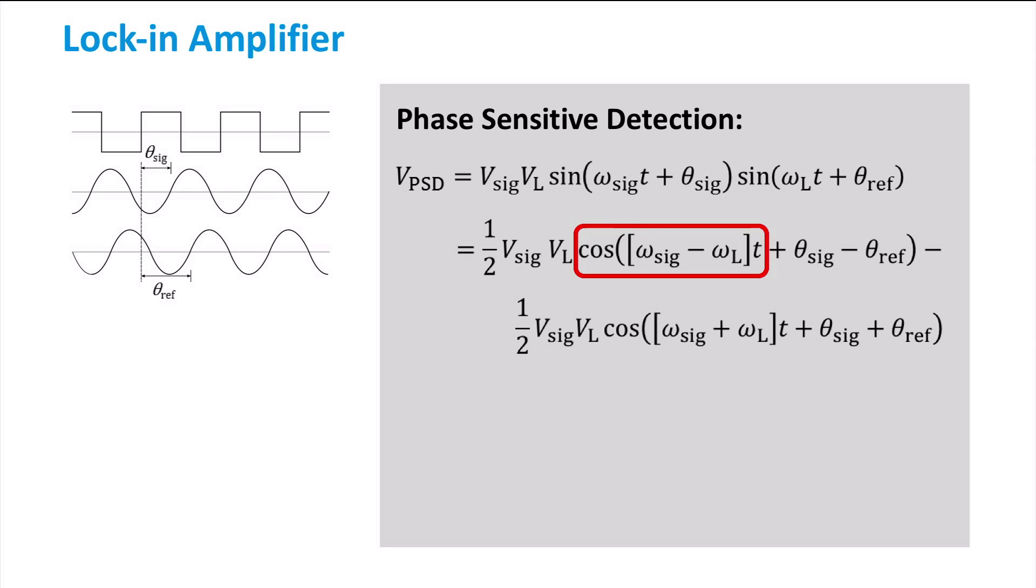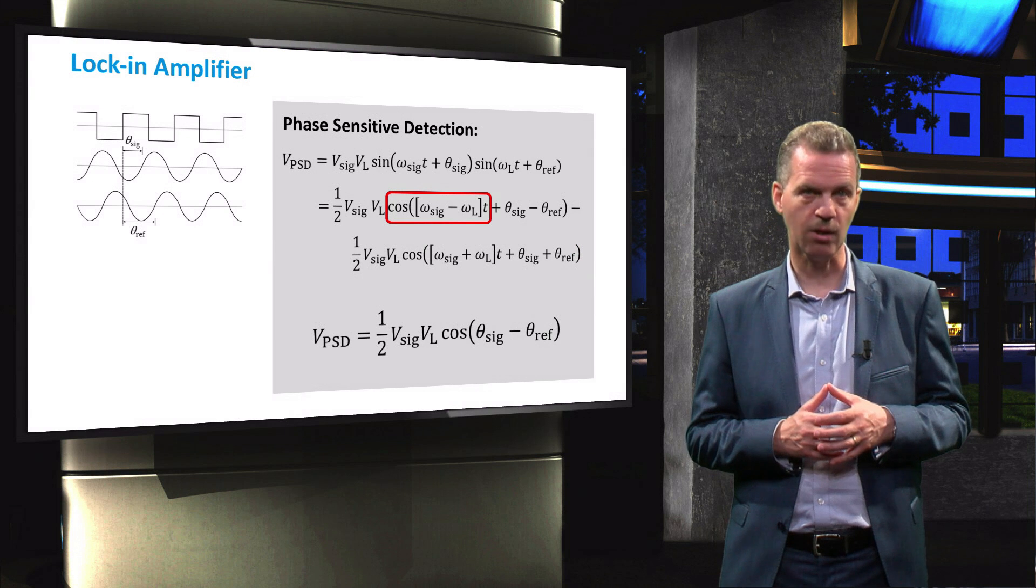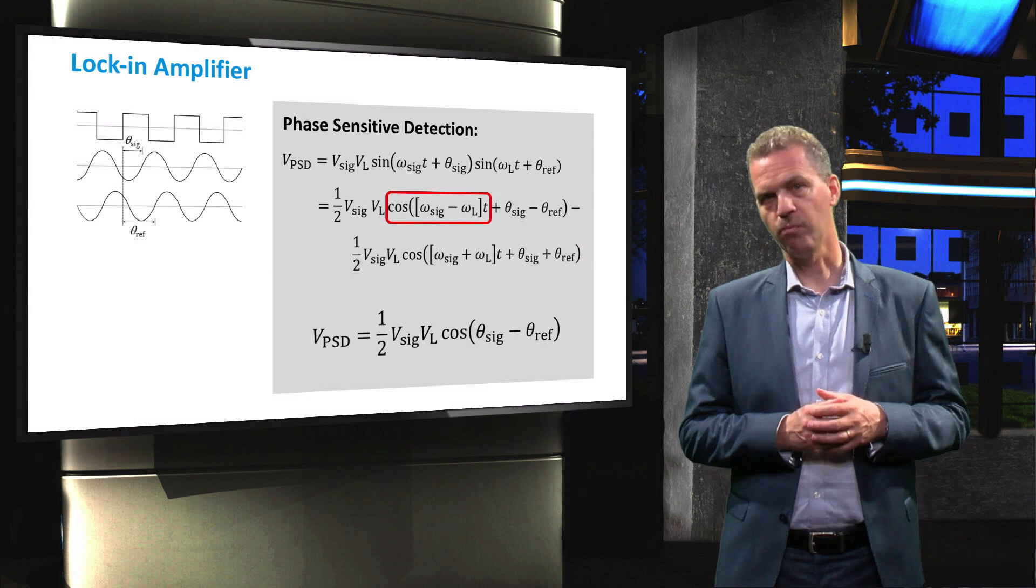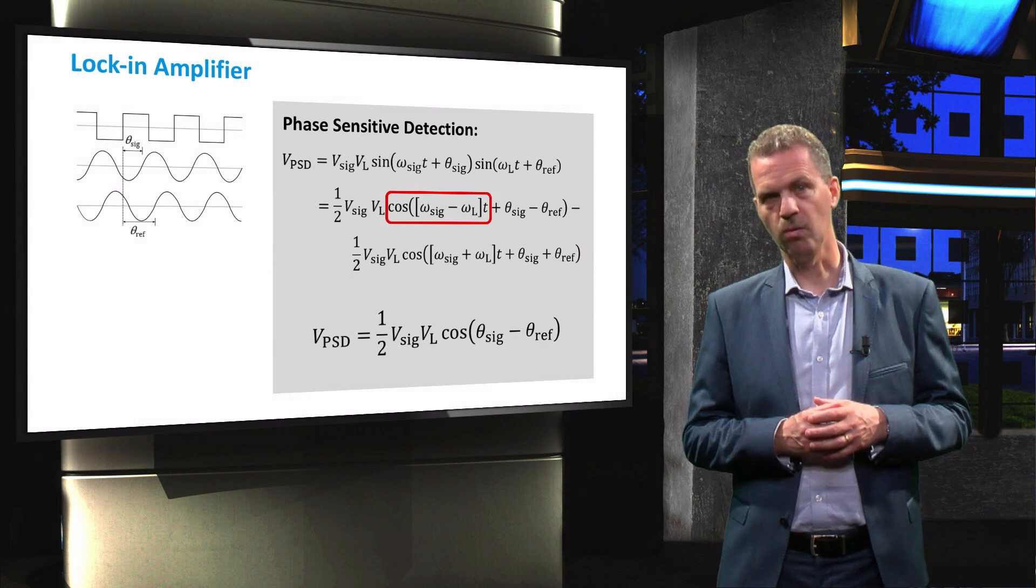However, we can see in the first cosine term that the frequency of the lock-in amplifier signal, omega L, is subtracted from the measurement signal frequency, omega SIG. These frequencies are only equal for the response signal with the chopper frequency. When these frequencies are equal, the cosine term becomes 1 and we arrive at the following DC signal. Thus, by passing the phase-sensitive detection signal through a low-pass filter, we obtain a DC signal that is proportional to the amplitude Vsig of the measurement signal in which we are interested. This is the reason why the probing light is chopped to obtain a measurement signal with a known frequency.